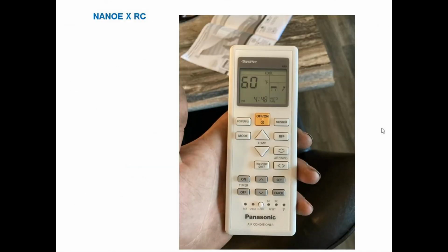And for whatever reason, if you don't have a phone, you don't have an app, all our error codes are listed on the right-hand side of the unit. On this cover over here, they are all the error codes. Then when you fix the error and you're done, it's good practice to erase the error code, so that next time when somebody else comes, they do not pick up your error code, because our unit stores at least one error code, and that error code is the latest error code. So it's a very good idea to erase the error code.